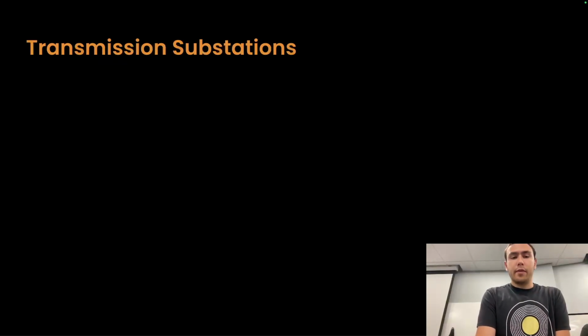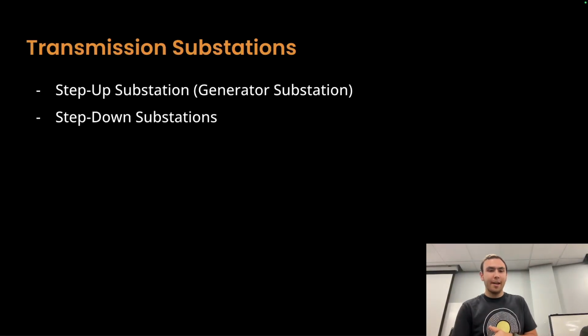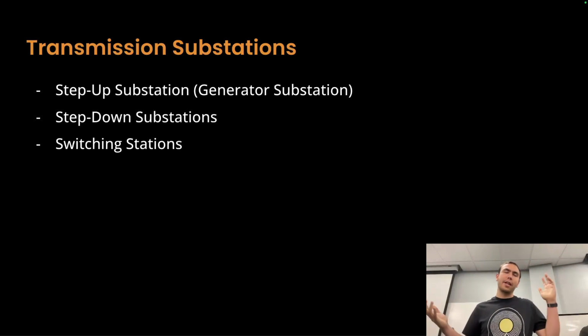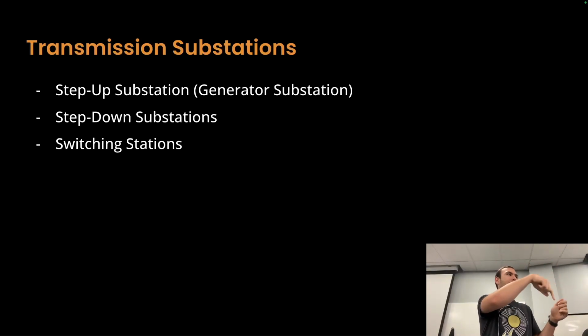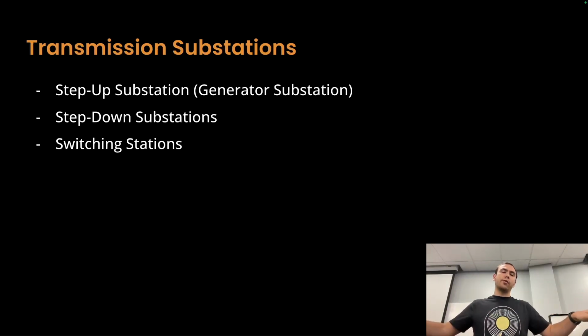Inside of the transmission system, we have transmission substations: a step-up substation, a step-down substation, and switching substations. We have transformers that step voltage up and down at the component level, but when modeling the entire electric grid, it's not practical to detail every individual transformer. So we break things up into substations, which use a variety of components and processes to either step voltage up, step it down, or switch connections to break up the circuitry of the grid.